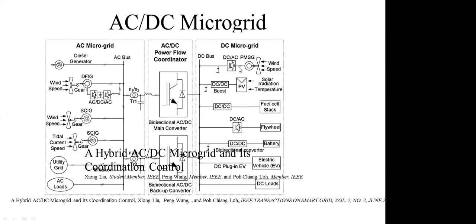I will not go into much detail here, I'm just mentioning what type of controls we are using. If you go for the grid connected mode, you use PQ control. In islanding mode, you can go for PV control. If you have fuel cells, or if you have two sources, you need to go for droop control.